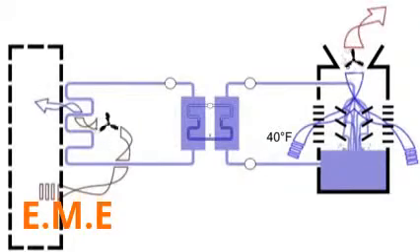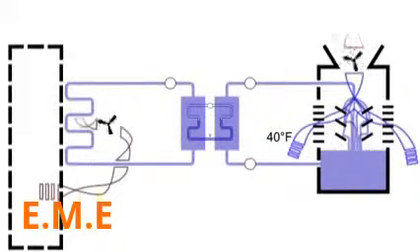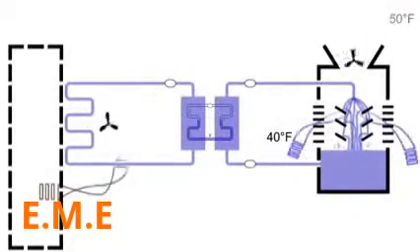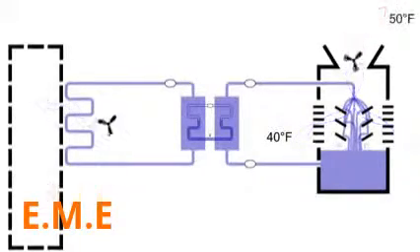Rather, the chiller is transformed into a simple heat exchanger, an intermediary exchanging heat between the chilled water loop and the cold water coming from the wintertime cooling tower.